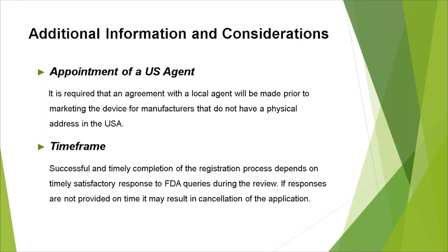And sometimes if a company submits documents that are sloppy or not consistent, like they'll have a different intended use on several submission documents, the reviewer will already take a negative approach, come up with a bunch of questions to stop the review, and they really don't want to approve your product. It's always good to remember that the technical file that you submit to FDA, the 510K, is going to give them an impression about how much you take quality seriously in your company and in your product.